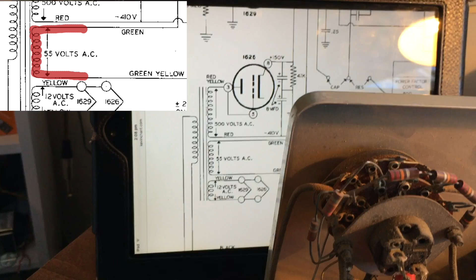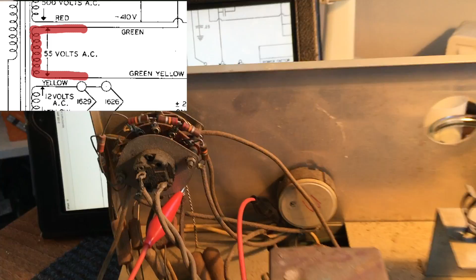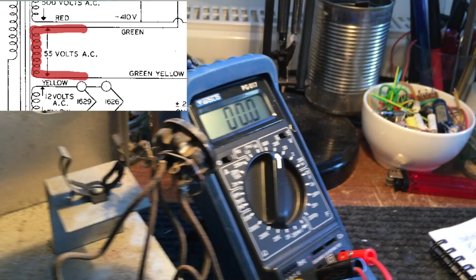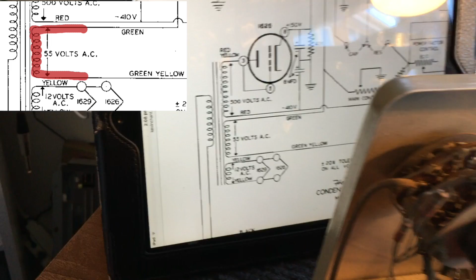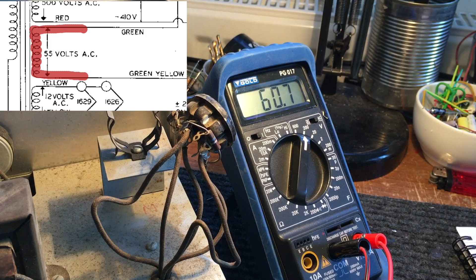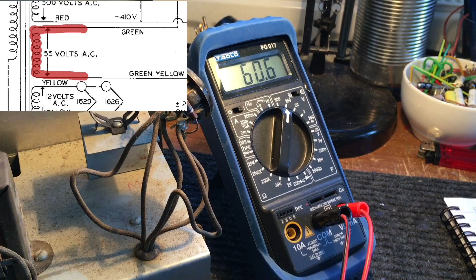The next step then will be the 55 volt green to green yellow. I'll make those connections. The green to green yellow connections made as before when checking the DC resistance. We're in the 200 volt range because we're expecting 55 volts AC, a bit more when unloaded. Off we go. Brilliant, look at that, 60.7 volts. Perfect, happy with that.